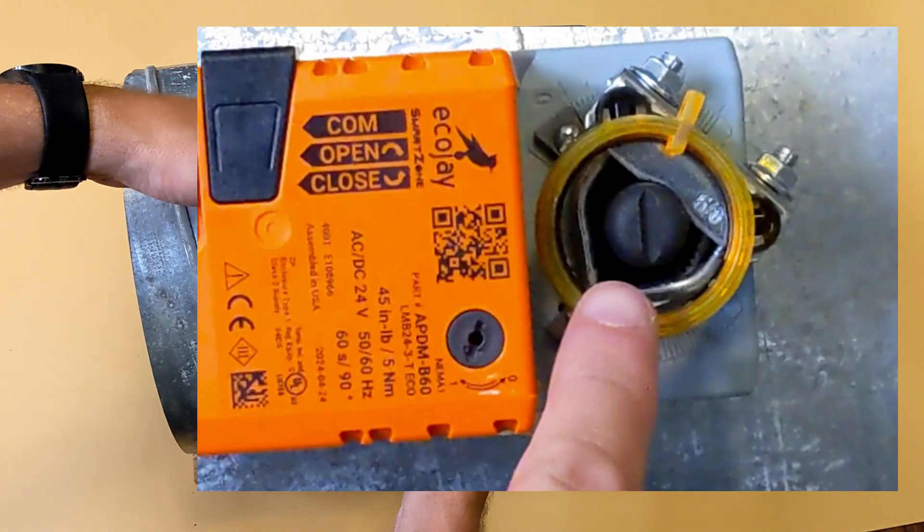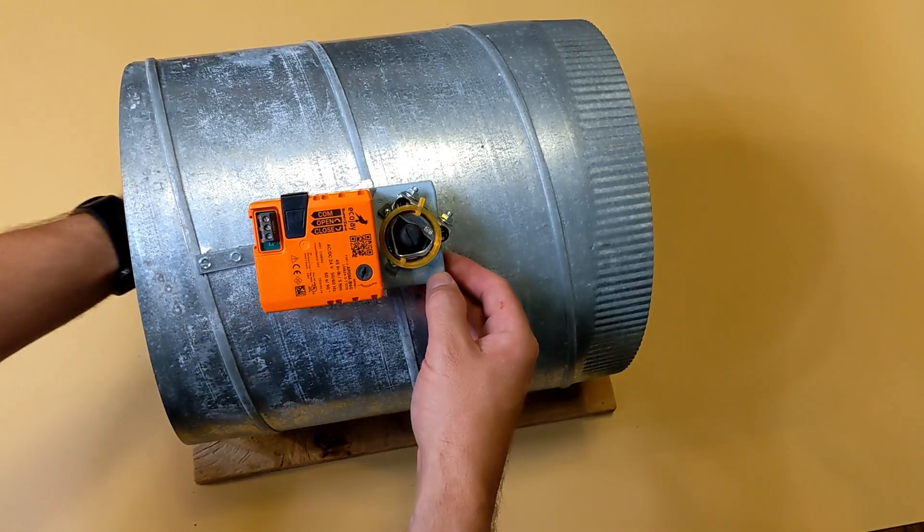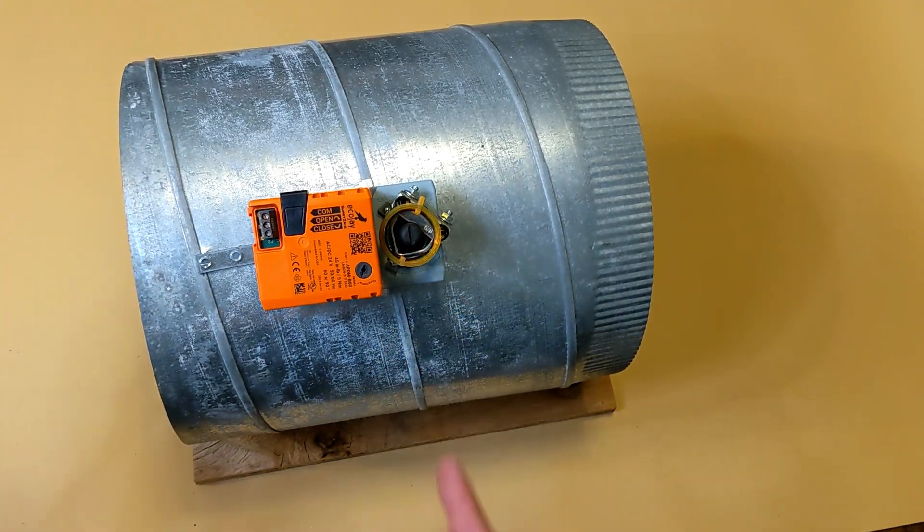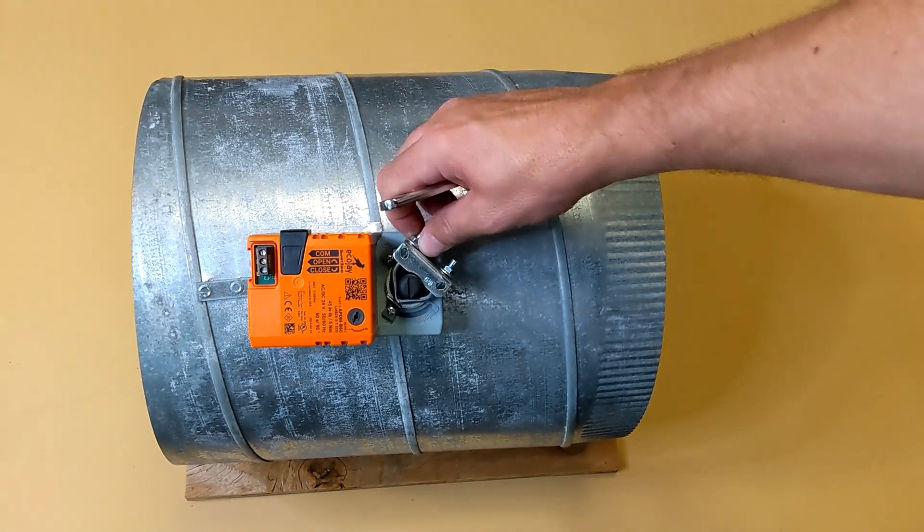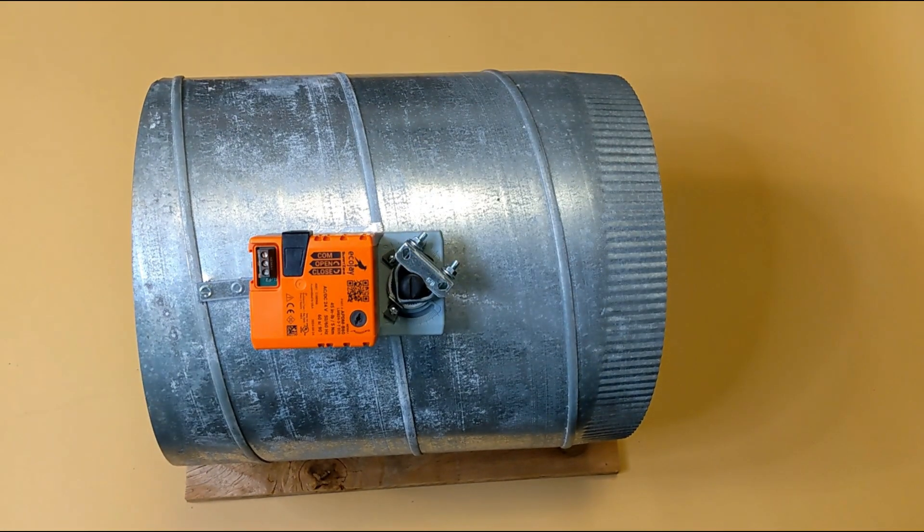Once you've ensured that the damper blade is in the closed position and that the damper motor is in the closed position, it's time to tighten the two nuts on the U-bolt. These should be tightened evenly until the U-bolt is snug on the shaft adapter.